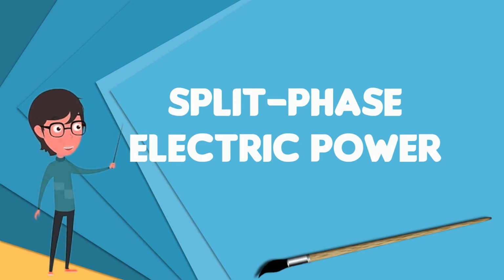The two 120 volts AC lines are supplied to the premises from a transformer with a 240 volts AC secondary winding, which has a center tap connected to ground. The system neutral conductor is connected to ground at the transformer center tap.